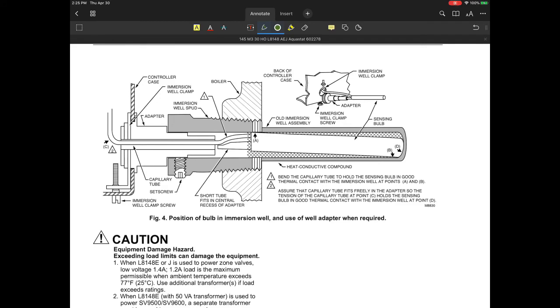The last thing that I want to get into that I think is imperative that we talk about is this. I want to show you the well. This particular insertion well, oftentimes, and you need to see this, is going to have an immersion well clamp screw that's shown right here. And it'll also have a set screw. This little immersion well clamping screw is a part that you have to not loosen. If you do loosen that one up, you can only pull it out a little ways, otherwise you're going to break the capillary tube that's going into the Aquastat device that they're identifying here. So you want to be very careful on that.